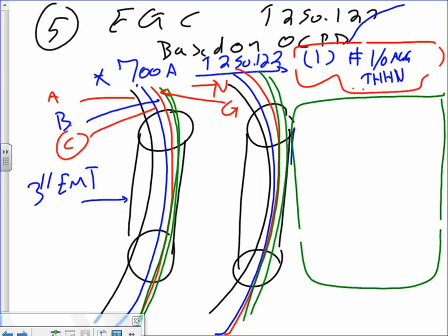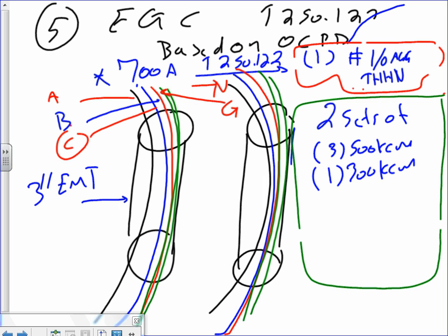THHN. Can you see where it's going to be inside? You will put the conductor inside each one of them. So your answer should be the following: 2 sets total. 3 conductors of 500 kcm, 1 conductor of 300 kcm, and 1 conductor of 1/0 AWG in every set. Am I making sense? 2 sets of the following.